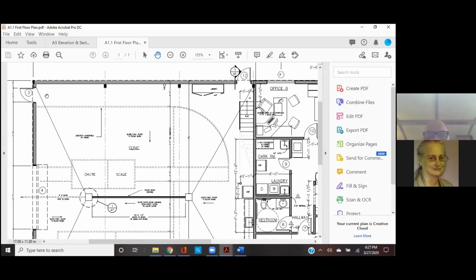So if you have a supply here and a supply here, you're going to make an L, come across there, and probably flex duct to those supplies. You're going to make a long L. And in the end, you can branch off anywhere you want after that point. When I'm standing with my back to the clinic here by this refrigerator, it's going to look like a W, right?